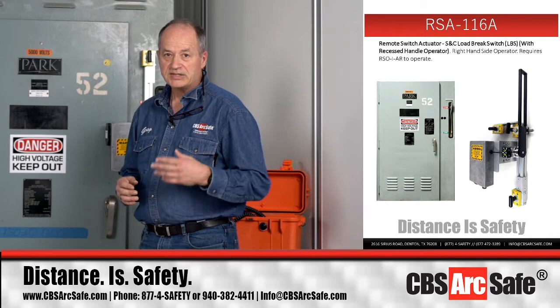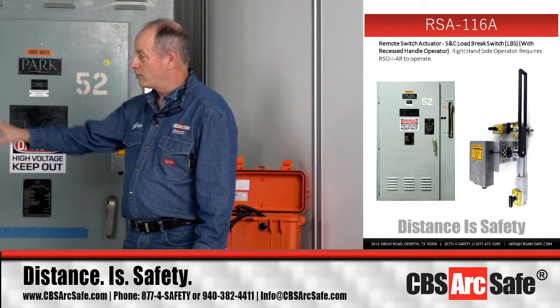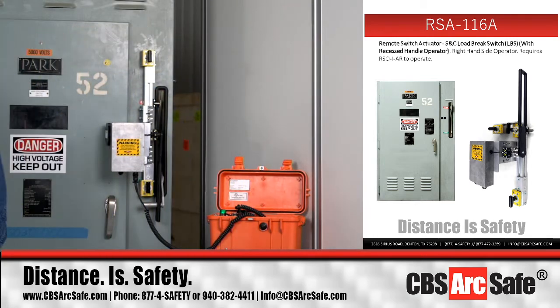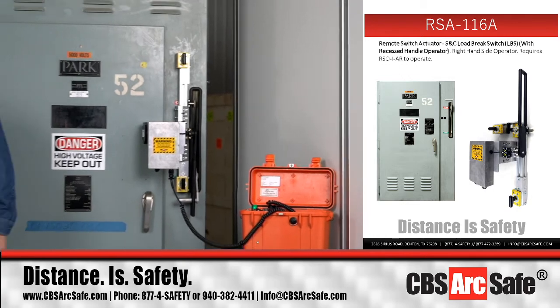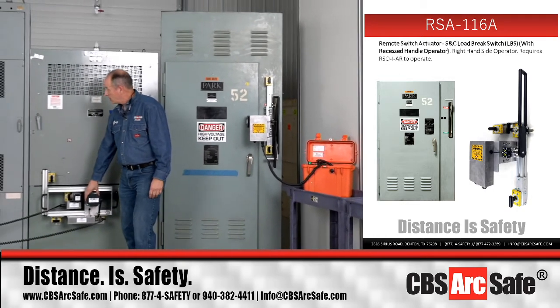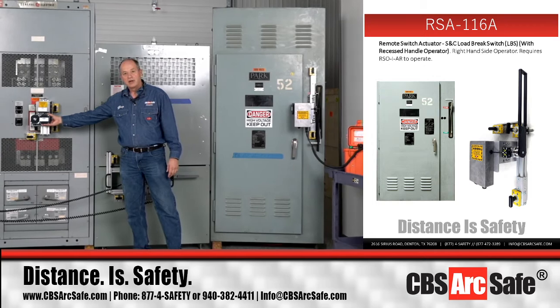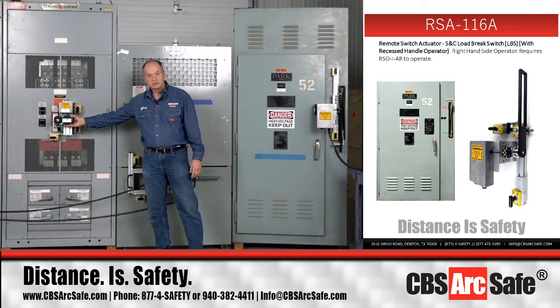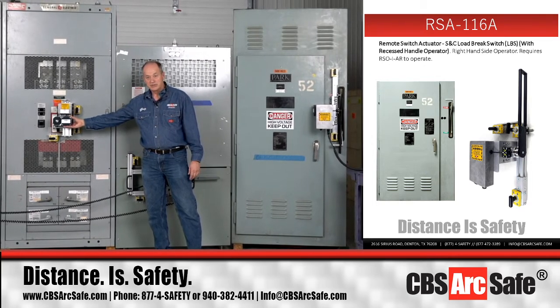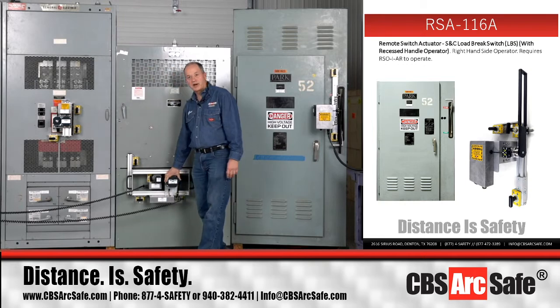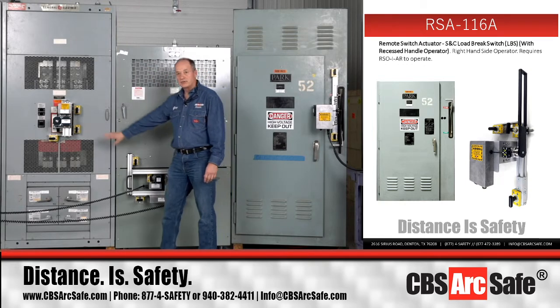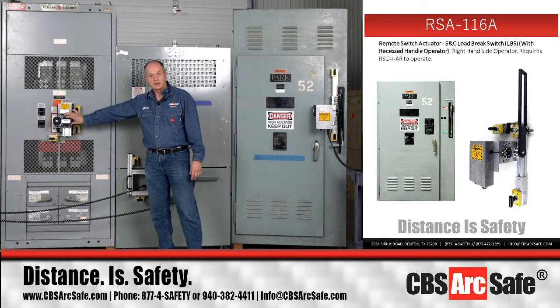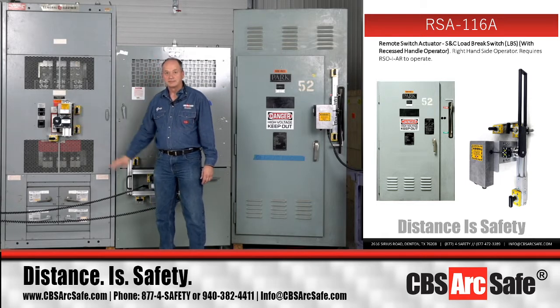So that's how we come up with how big a motor we use, because you'll notice here, if we look at the one on our Boltswitch, it's much bigger than the one on our HPC switch. And there's a reason. This is a much stouter operating mechanism in terms of the forces required to charge and close the breaker.